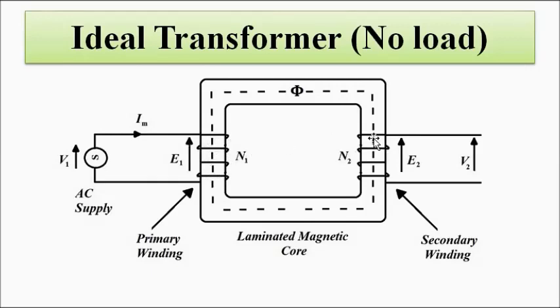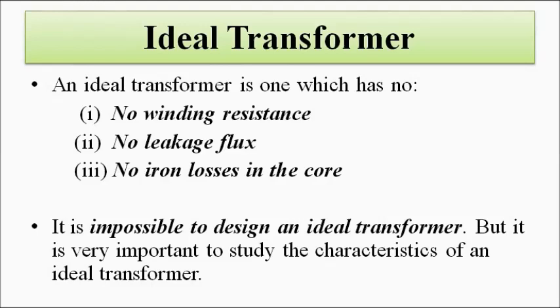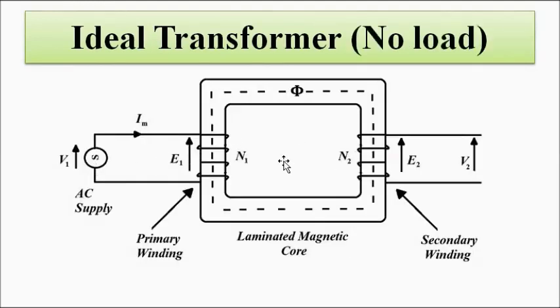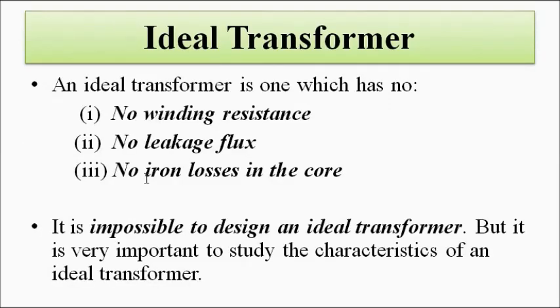Mutual flux is the flux produced in a winding that links with the other winding — it is the common flux. In an ideal transformer, all the flux generated links with both windings. In reality, there will be leakage flux. Also, in an ideal transformer there are no iron losses such as eddy currents and hysteresis losses, but in a practical transformer these do occur. It is therefore impossible to design a truly ideal transformer.